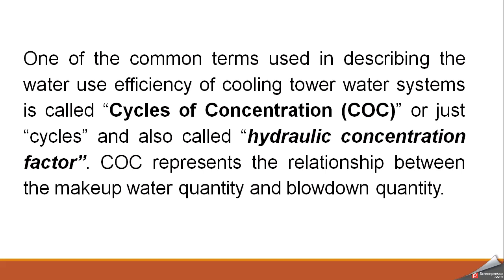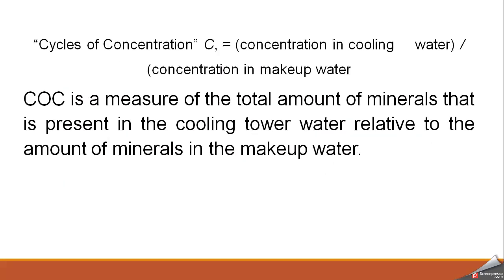So this is basically the ratio of these two quantities, the water we make up and the water we discard or blow down during the operation. So cycle of concentration is basically the measure of the total amount of minerals present in the cooling tower water relative to the amount of minerals present in the makeup water.